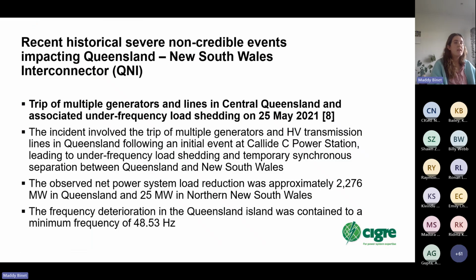In terms of recent events where the Queensland to New South Wales interconnector tripped, one of the most significant was the trip of multiple generators in central Queensland, which also resulted in significant under-frequency load shedding, occurring on the 25th of May 2021. AEMO publishes detailed incident investigations, and that report is publicly available on the AEMO website. I believe CS Energy has also published an incident report, so there's a lot of material available if you want more details.